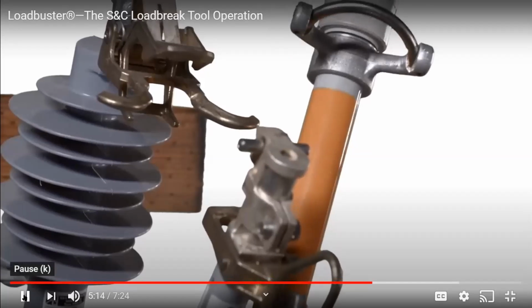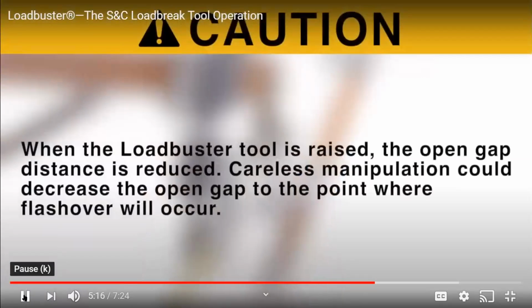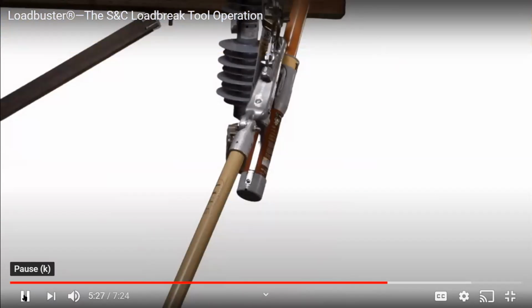Anchor from the attachment hook. When the loadbuster tool is raised, the open gap distance is reduced. Careless manipulation could decrease the open gap to the point where flashover will occur. Next, bring the fuse toward its fully open position.